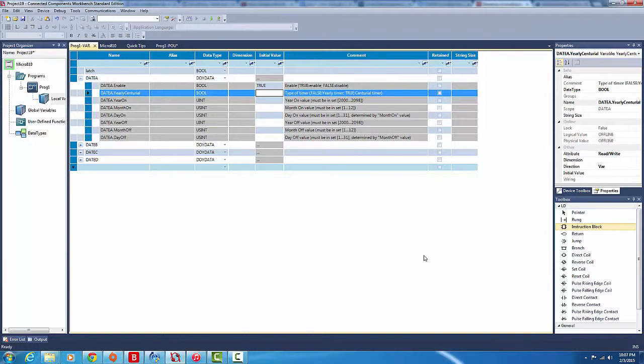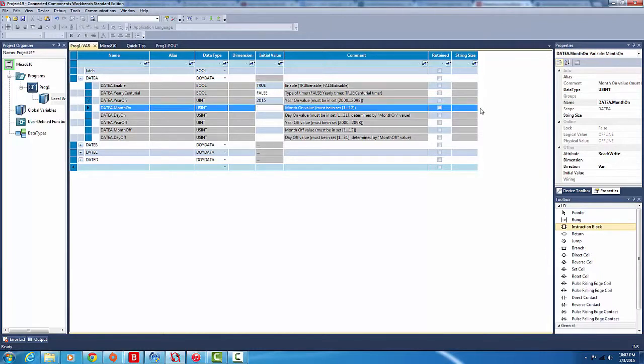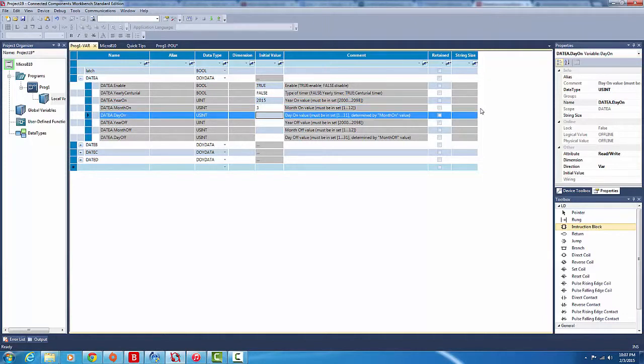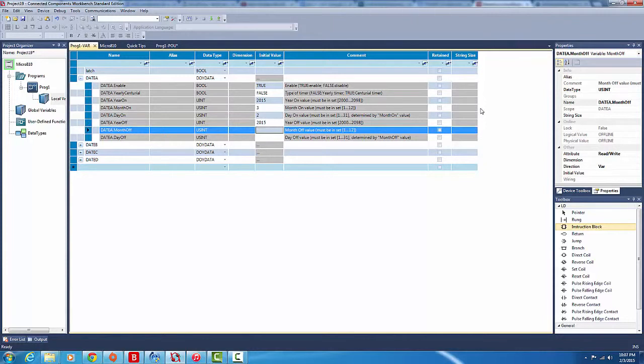Let's get started. We'll make this a yearly timer, so make it false. The year we want to turn on is this year, 2015. Just for the sake of showing you guys how it works, I'll put in today's date, which is the second of the third. So month is the third and day is the second. For when it turns off, we're going to make it 2015. Let's say we wanted to run for three more days, we're going to type in the value five.